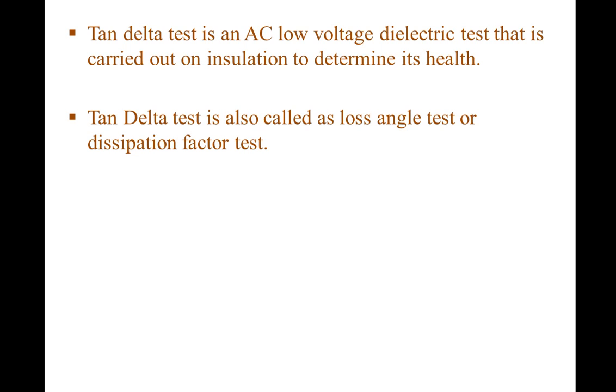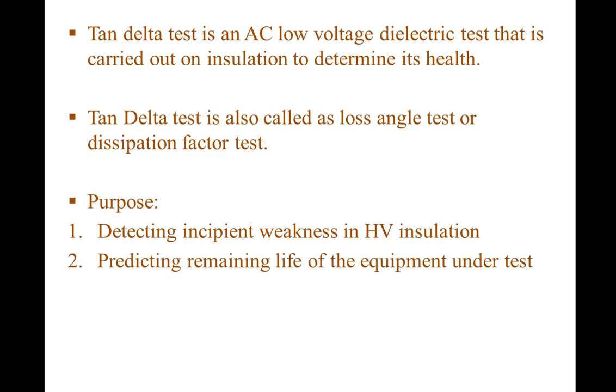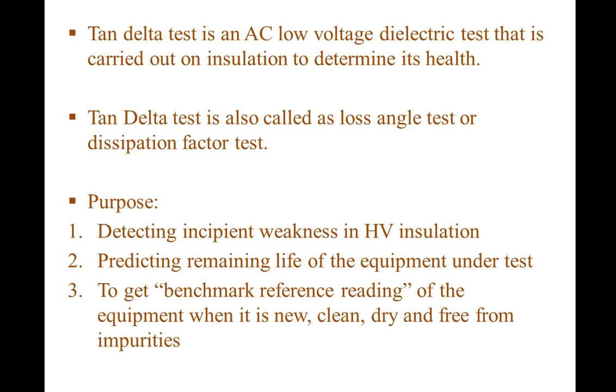The purposes of doing tan delta test are: detecting incipient weakness in HV insulation — incipient weakness means slowly growing weakness in the insulation — predicting the remaining life of the equipment under test, and to get a benchmark reference reading of the equipment when it is new, clean, dry, and free from impurities.